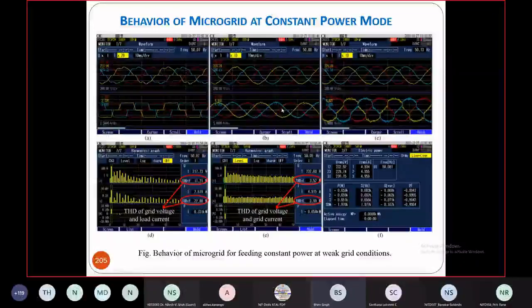But when you put this converter control, the grid current can be maintained sinusoidal, and load compensation can be provided by that inverter - these are the inverter currents. So the inverter is not only generating power, but it is also providing the harmonics to the load, and because of that local supplying of harmonics to the load, now voltages are not distorted.